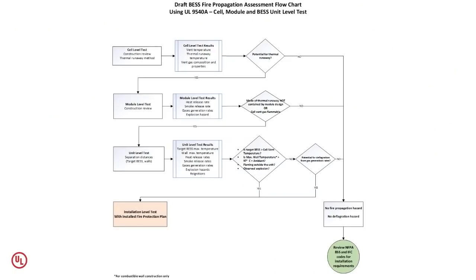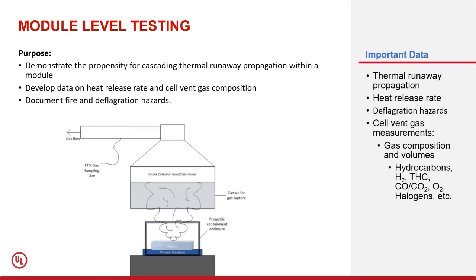Again, if we follow the flow chart, we saw the off-gassing, the transition to thermal runaway, so we're going to go to the module level test. That module level testing is again under the cone calorimeter. We're also trying to capture a lot of the same data that we caught from the cell level test: the thermal runaway propagation, the heat release rates. We're looking for deflagration hazards and also the gas measurements, composition and volumes.